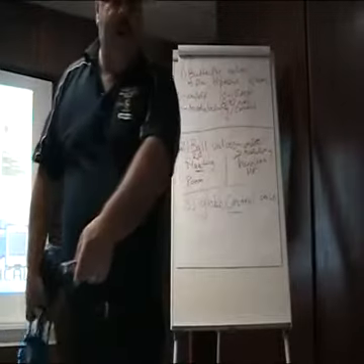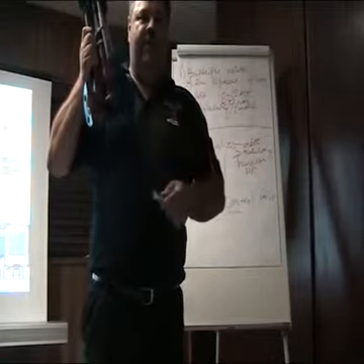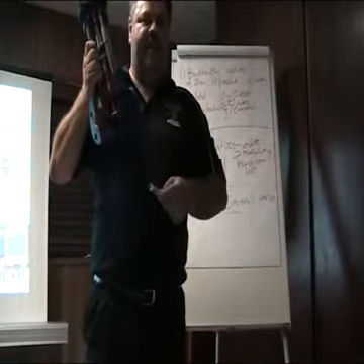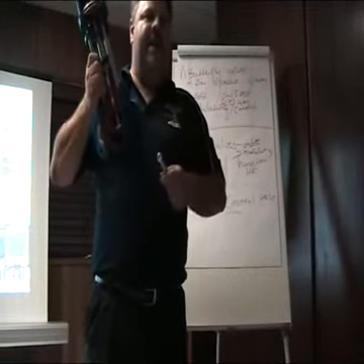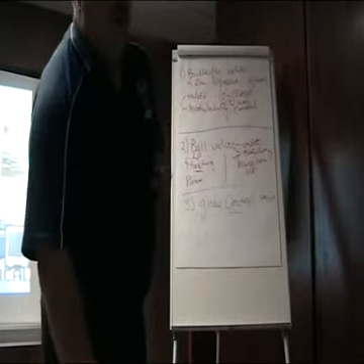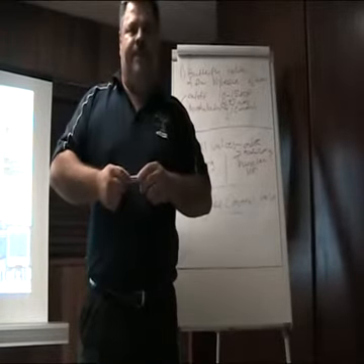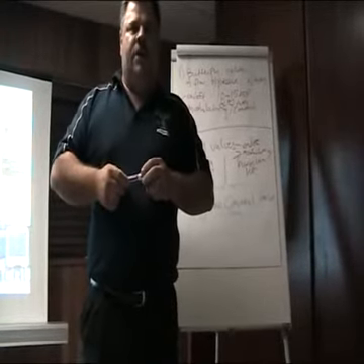You're not going to be able to handle that with other valve types. You're going to have to change something inside this valve to make it go lower than 85 decibel. And that's what David's referring to. You can't do that in a ball valve, you can't do it in a butterfly. In the globe valve, you can put fancy trimming. But in a ball and a butterfly, you cannot put fancy trimming.